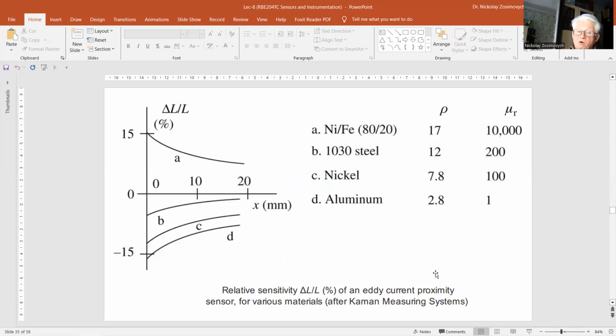The self-inductance of a coil not only depends on the lift-off distance to a conducting target, but also on the conductivity of the target, as you can see in this figure. This property is exploited to measure liquid level and liquid conductivity at the same time, using two coaxial coils located above the liquid. A model-based approach is followed to infer both quantities from the frequency-dependent imaginary part of the impedance.